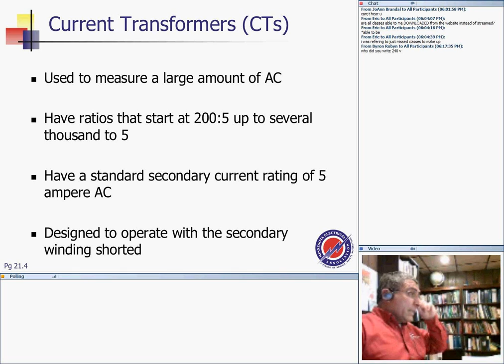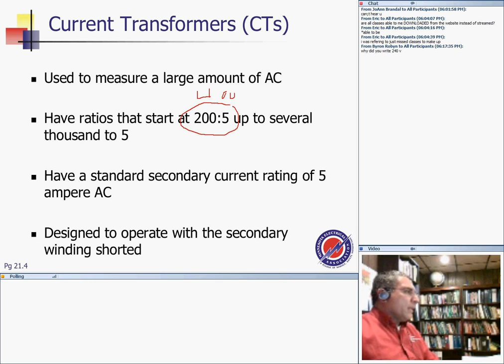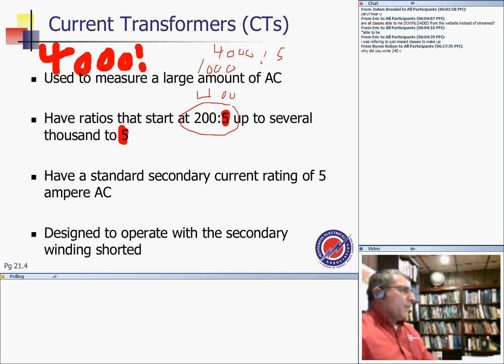CT is commonly used, and you can find a CT that can convert 200 amps to 5. Rated 200 to 5, so you can load them up to 200. If your system is higher than that, then you go 400 to 5. If your system is 1000, you go 1000 to 5, and all the way up to 4000, which we install a few of, 4000 to 5. It's the industry standard in the American system that the secondary is always 5. The primary can change. I can have a 4000 amp CT, but the secondary has to be 5, because the equipment that we have cannot handle more than 5.